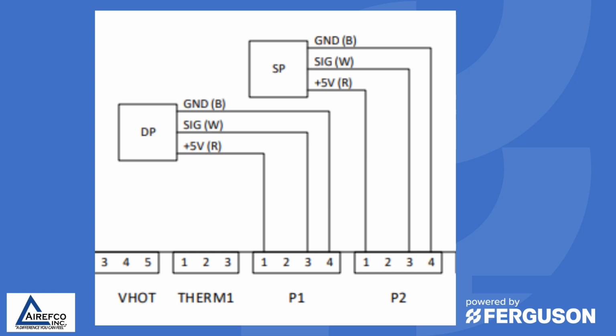So in this wiring diagram, we see that the discharge pressure transducer is tied into P1 plug, and the suction pressure transducer is tied into P2. As we previously stated, these pressure transducers can be interchanged. So if you suspect one of the pressure transducers to be defective, by switching the plugs between P1 and P2, if the problem stays with the transducer, that means the transducer is bad. If it doesn't, then there could be a wiring issue that's going on and you're not getting the proper voltage through the wiring harness back to the control board.